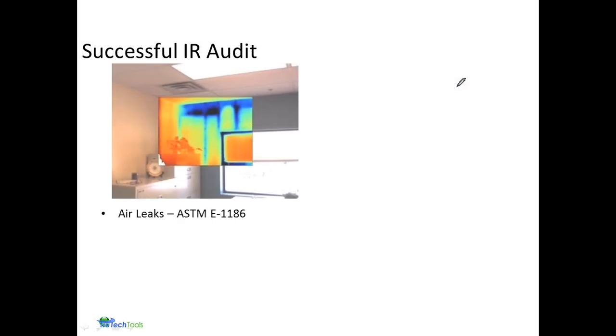A successful audit requires understanding the conditions for an audit. If you're checking for air leaks, RESNET suggests a delta T of at least 3 degrees, meaning a difference of temperature between outdoors and indoors. If the outside and inside temperatures were the same, you simply wouldn't see a thermal difference at all, and if that difference gets too small, it becomes very difficult. So for air leakage, we want at least 3 degrees difference, if not more.